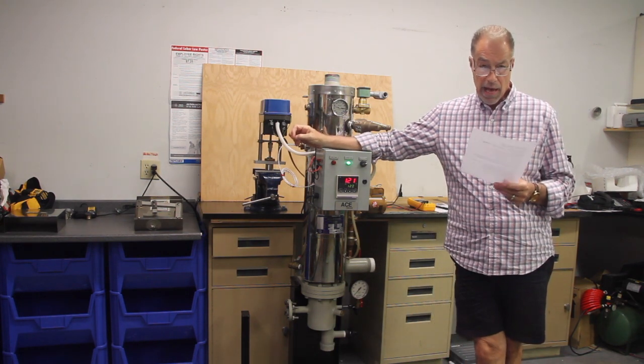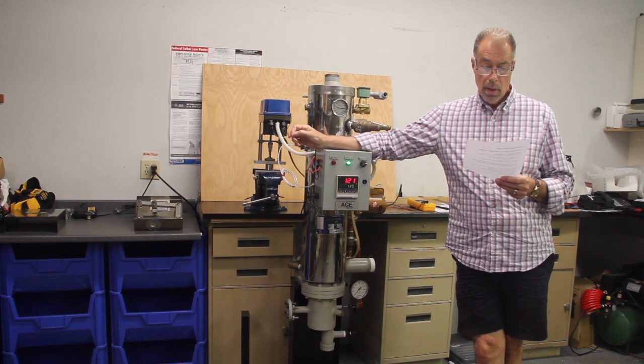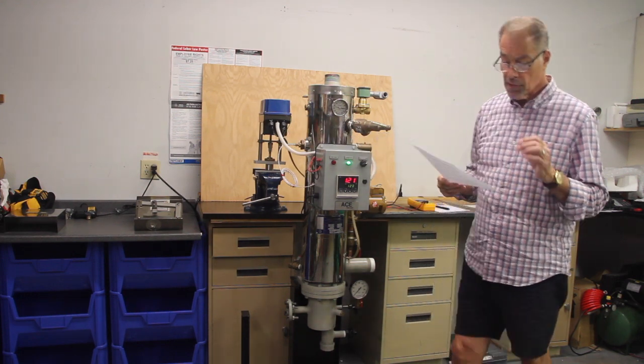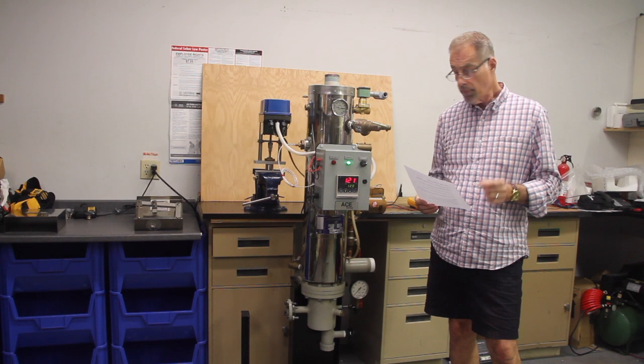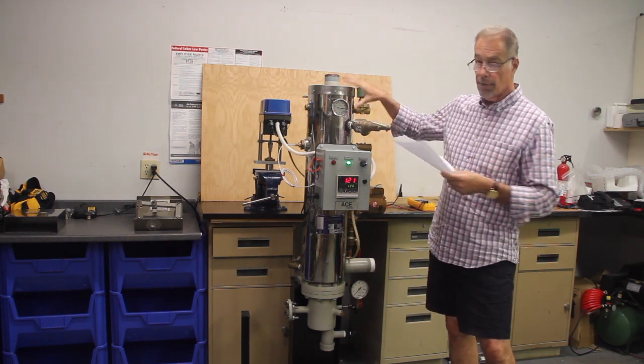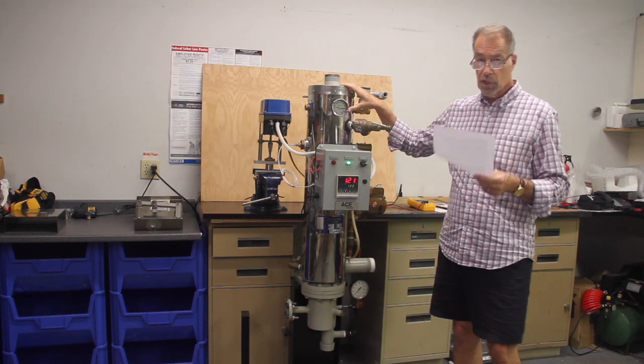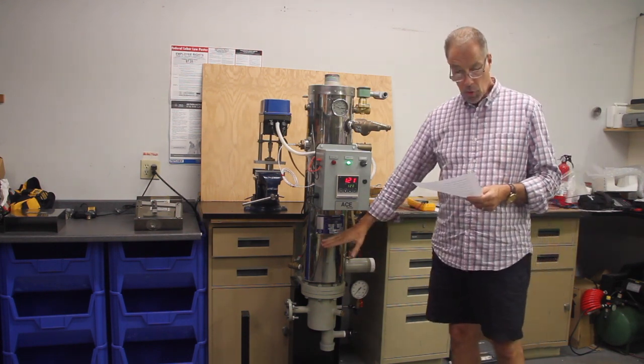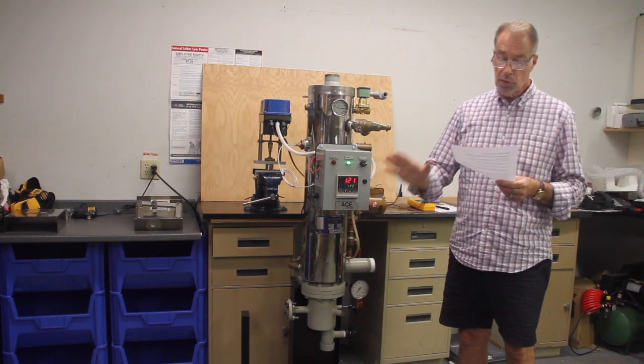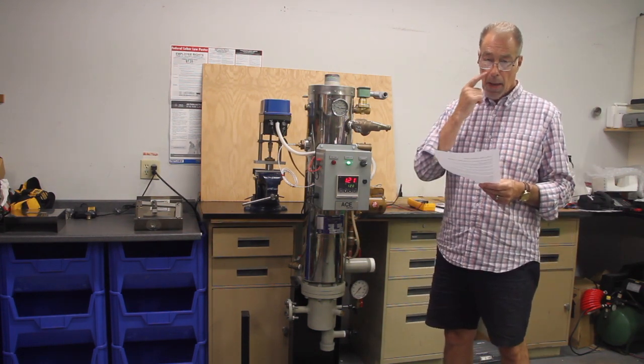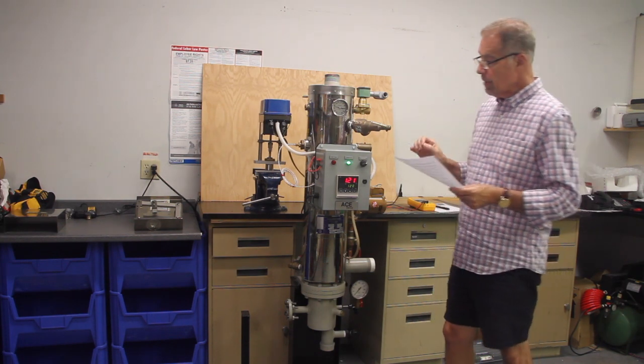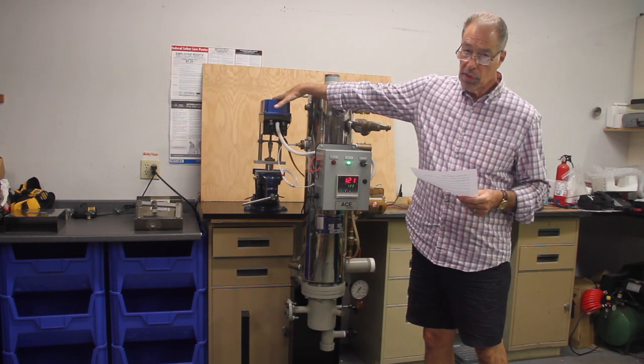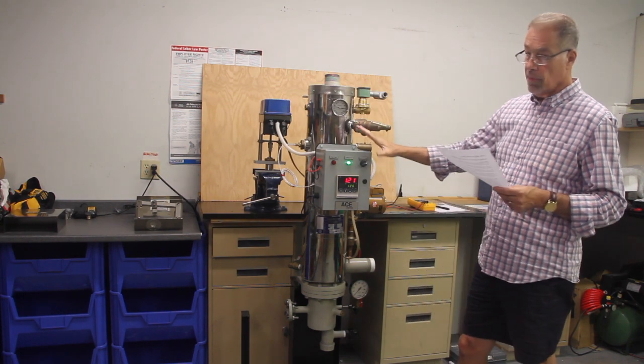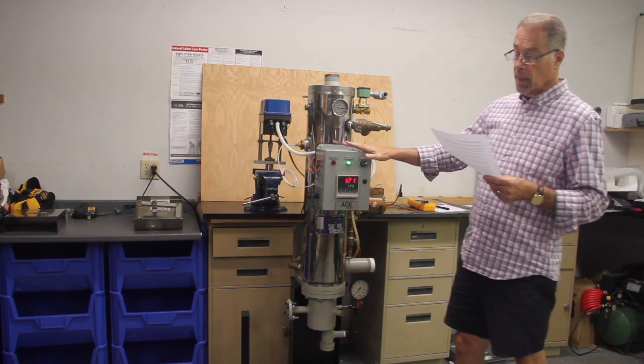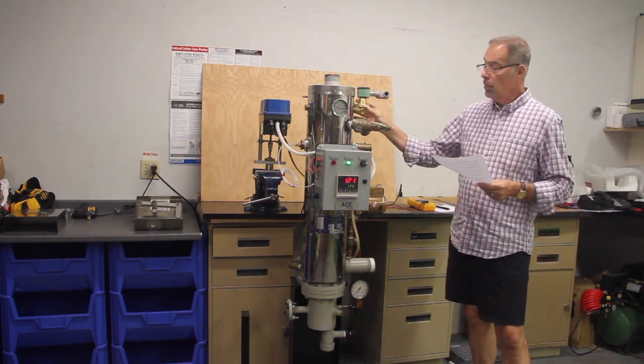They're model SI-V8 SW SE 250-D. And what that means is SI is semi-instantaneous, V is for vertical, 8 is for the diameter of the shell, SW means single wall. The tubing, the U-tube here, the copper tubes, are single wall versus double wall. Dash SE, the S means steam, the E means electronic fail-safe actuation, an electronic NEMA 1 or 4 control panel. And the dash D means a double solenoid safety.